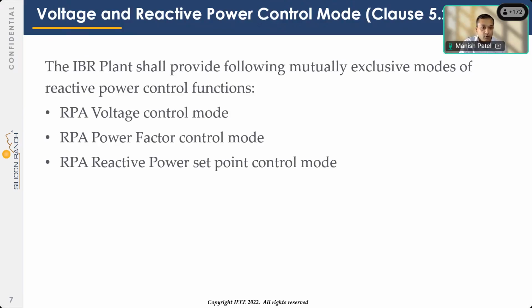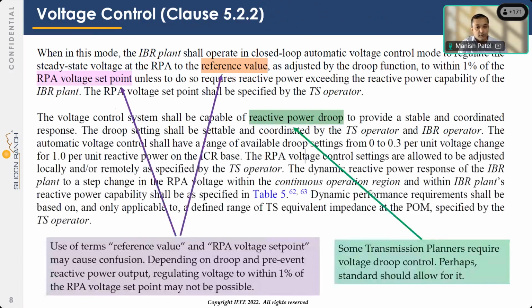So today I'm only going to talk about this voltage control mode option. I do have some thoughts on power factor and reactive power control mode also, but in respect of time, just the voltage control mode. So this is the language in a voltage control clause 522. It says the IBR plant shall operate in closed loop automatic voltage control to regulate the steady state voltage at the RPA to the reference value as adjusted by droop function to within 1% of RPA voltage set point.